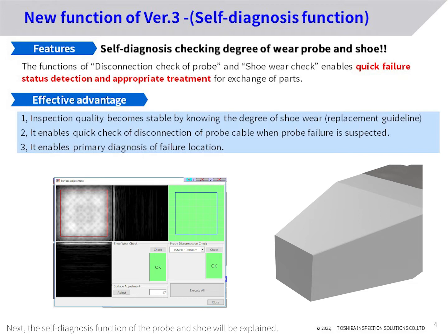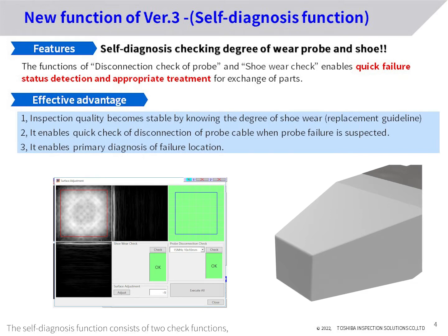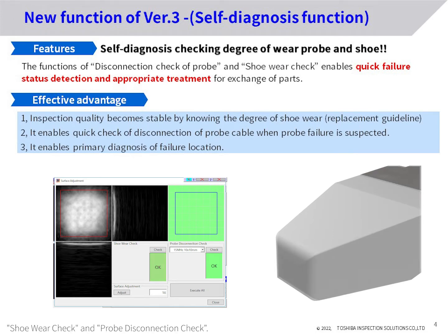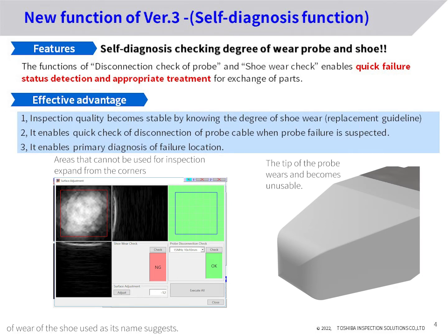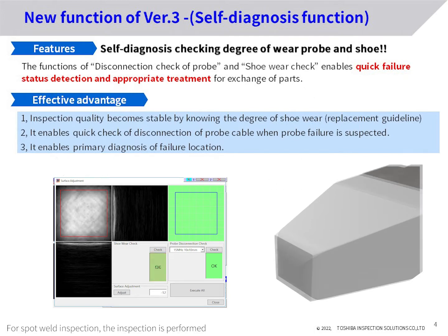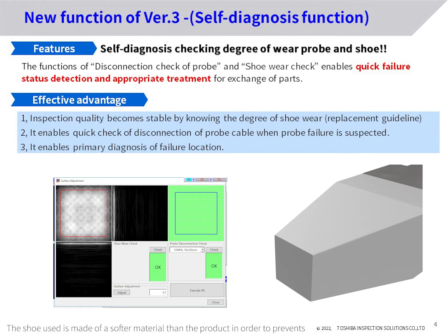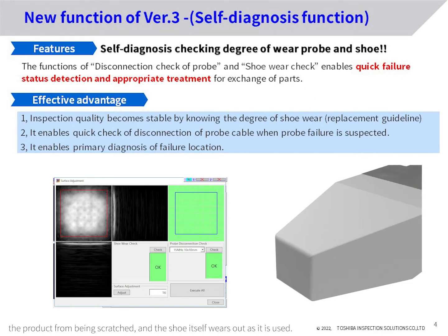Next, the self-diagnosis function of the probe and shoe will be explained. The self-diagnosis function consists of two check functions: shoe wear check and probe disconnection check. The shoe wear check function can check the degree of wear of the shoe. For spot weld inspection, the inspection is performed after attaching the shoe to the ultrasonic probe. The shoe is made of a softer material than the product to prevent the product from being scratched, and the shoe itself wears out as it is used.